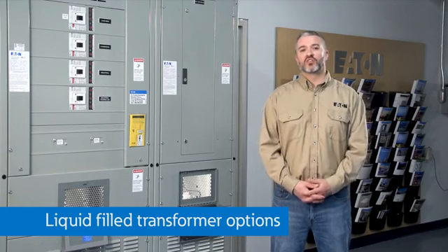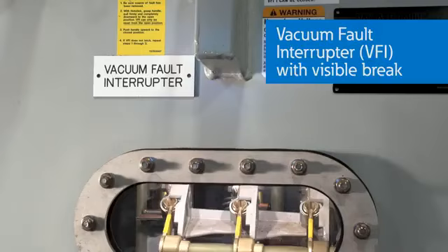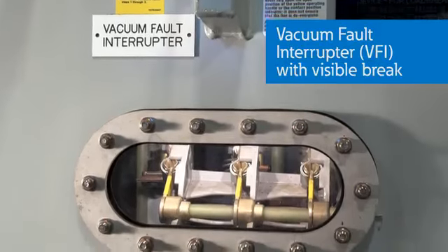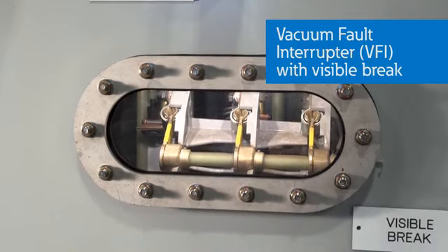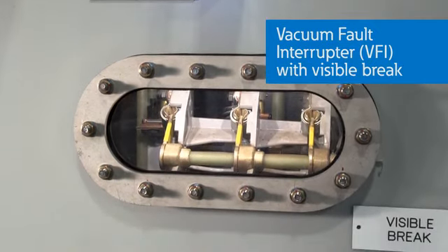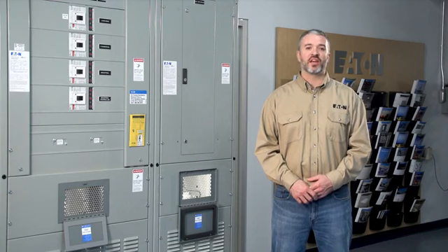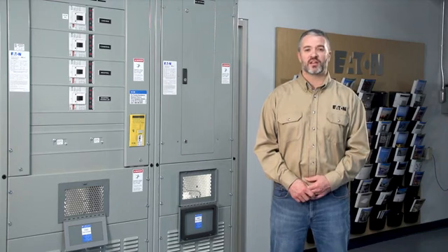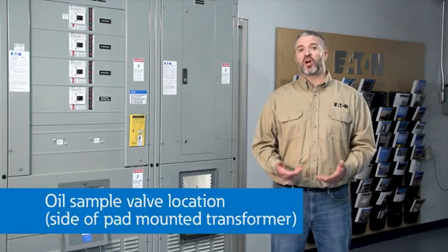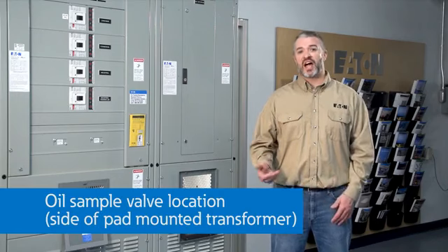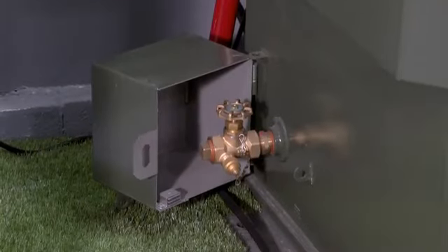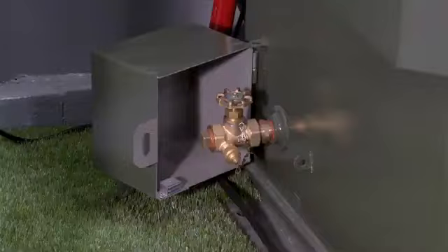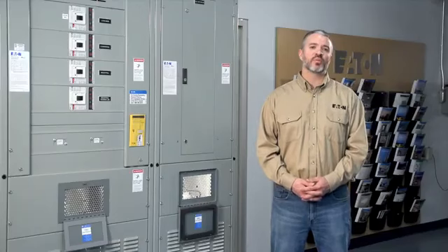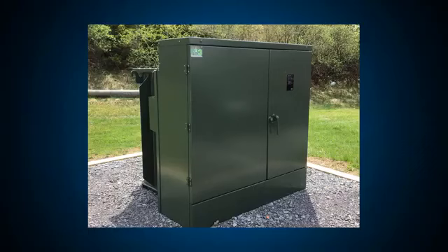For liquid-filled transformers, you might want to consider a vacuum fault interrupter or VFI option like this one, which allows you to have the primary protection device, a vacuum breaker, installed in the tank along with the visible means of disconnect. In addition, you can also put the oil sample valve on the side like this transformer instead of behind the door. This allows you to do oil testing without opening the transformer doors on a pad-mounted transformer like this one. As you can see, there are many solutions for arc flash.